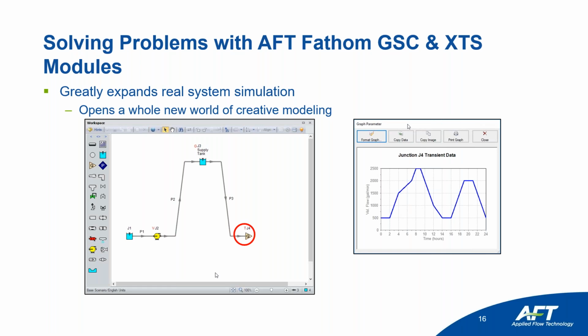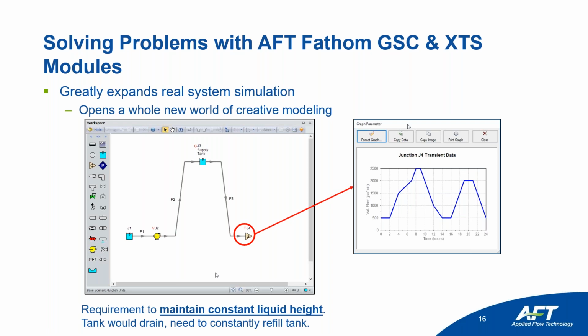So this is actually how my flow rate changes at that location over a day period. This is your flow demand, okay? So over 24 hours, you have an increase in flow at a point in the day, and it drops off, and then you have another increase in flow. So that's how my flow rate is changing over time. Well, the next thing is I have a requirement where my liquid tank supply or my liquid tank height needs to be the same. I don't want it to drain. So the liquid height there needs to stay constant. The way that I'm going to do that is by using the goal seeking control module. I'm going to vary the pump speed in order to maintain a constant liquid height for my supply tank.